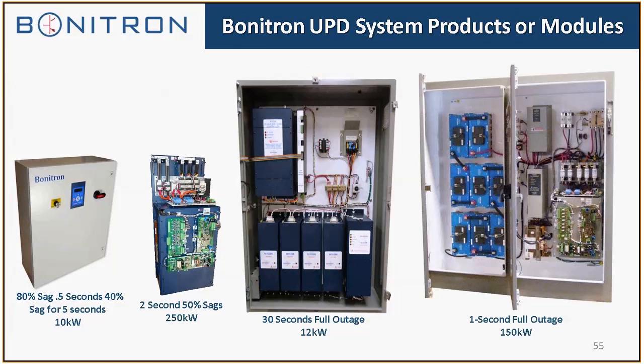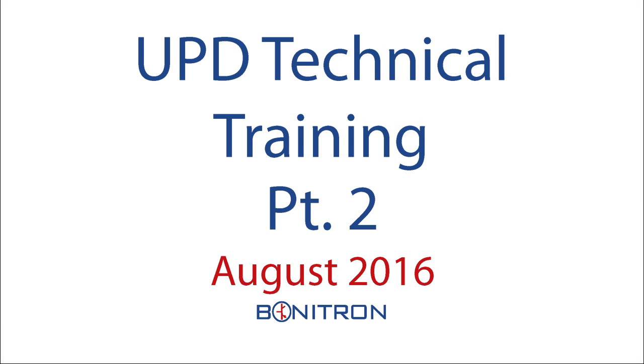This shows a correspondence between the smaller cabinets, 10 to 50 kilowatts, where energy storage and the electronics can go in one cabinet. And then the 2-second SAG single units that can go in the VFD cabinet. And that shows the one in the middle, 12 kilowatt, which is a battery system. Here we provided the battery modules from us because it was a smaller system. Usually for the big cabinets, we go out to a battery vendor. For the smaller 50 kilowatt and below, we'll provide our own battery modules and source the batteries only. And over on the right is the 1-second full outage 150 kilowatt.